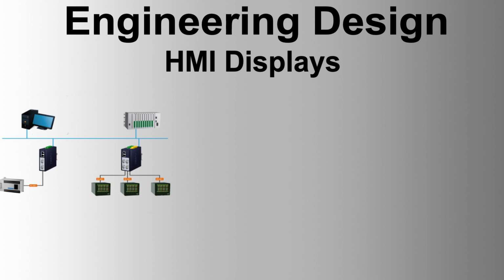Configuration standards. Colors. Color usage should be conservative to avoid clutter and strain on the eyes. Prominent colors should be reserved for urgent situations. Color should not be the sole means of distinguishing important items and states. It should be used together with other highlighting features. Typical color conventions include red, high priority alarm indication; yellow, medium priority alarm indication; green, healthy logic signals; cyan, magenta, white, various normal and fault indications.